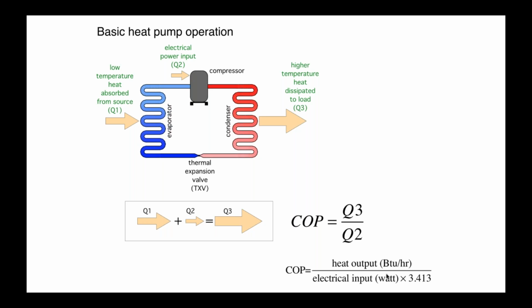Now, I want to stress to you, a COP is an instantaneous performance index. If any of the operating conditions change, such as the outdoor temperature or the water temperature leaving the heat pump, that is going to change the COP. So don't say that you have a heat pump with a COP of 3 or 4 or whatever the number is. That's a snapshot. That COP is going to vary considerably, even over an hour's worth of operating time, depending on, again, changes in outdoor temperature or water temperature.